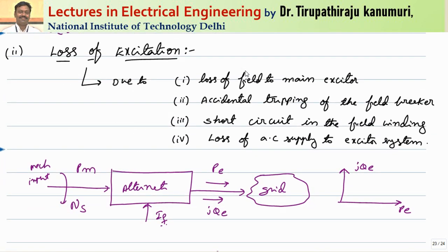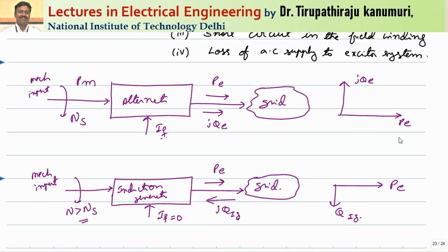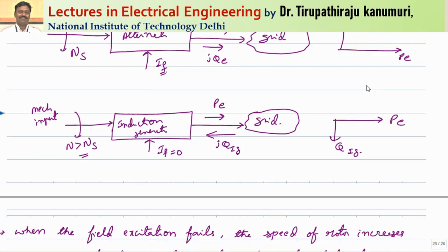The second type of problem in the rotor is loss of excitation. This can happen due to loss of field to the main exciter, accidental tripping of the field breaker, short circuit in the field winding, or loss of AC supply to the exciter system. Under normal operating conditions, field current is present, mechanical input PM is given, the rotor rotates at synchronous speed NS, and the alternator produces both active and reactive power supplied to the grid.